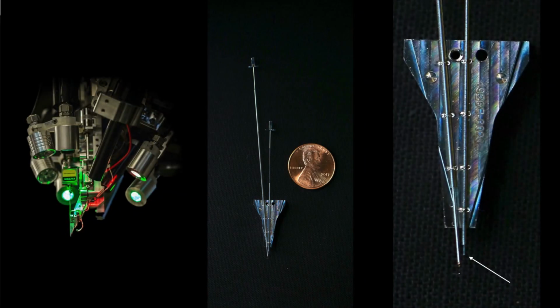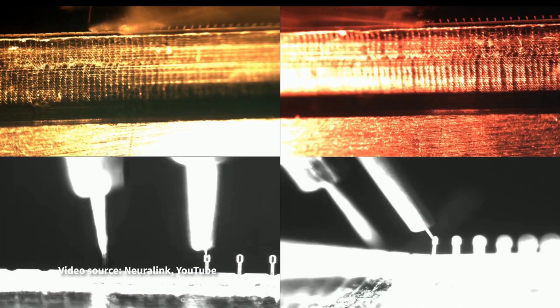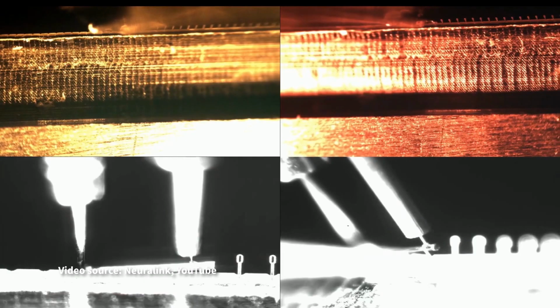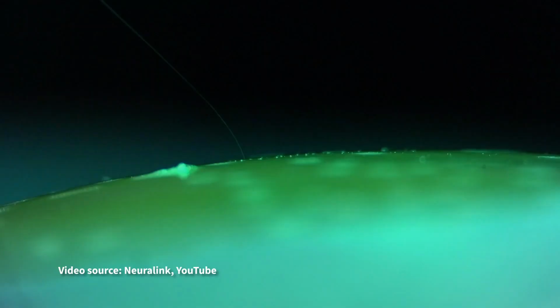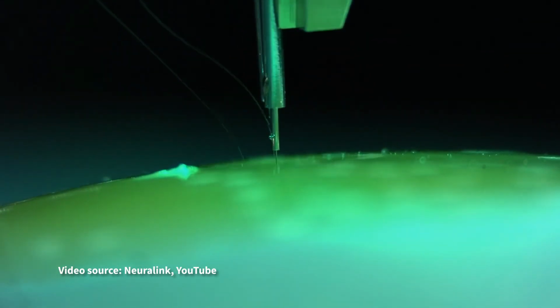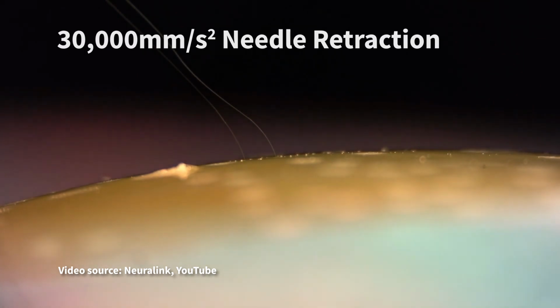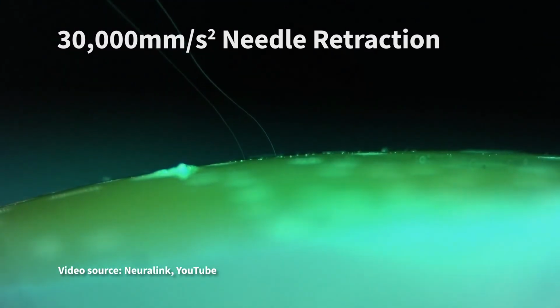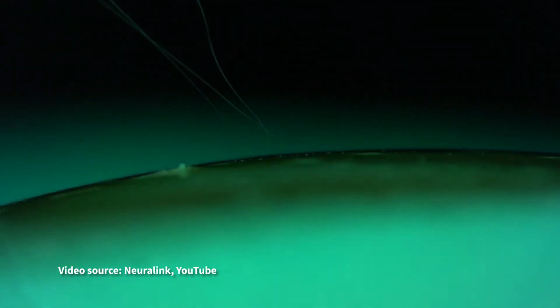The end effector holds what they call a needle pincher cartridge, or an NPC. This penny gives you a sense of size of the needle. The needle's purpose is to both hook into the probe loops for transport and to penetrate the brain tissue. It's driven by a linear motor and rapidly retracts with an acceleration of 30,000 millimeters per second squared to encourage the separation of the probe from the needle.